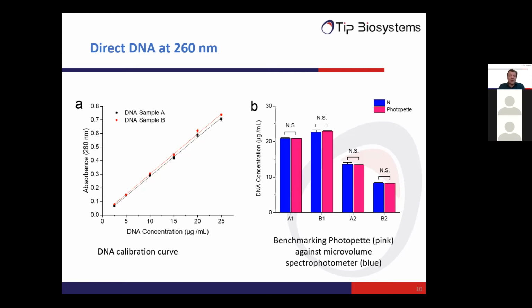which is performed at 260 nanometer. So you can do this directly in the tube or the sample container where you have your DNA. No sample transfers necessary. Also, the sample loss is very, very minimal. I mentioned to you before that the sample enters the cuvette tip, but if you remove the cuvette tip from your sample, that amount of liquid is flowing back and remains in your sample container.